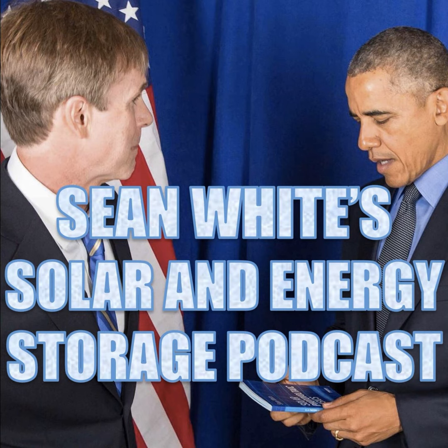Still, it's good to go back to Article 690 to learn some things, because we can see some images there which they don't have in Article 706, Energy Storage Systems. There's also Article 480, called Storage Batteries. I know it's kind of confusing - there are two different competing articles, one for batteries, one for energy storage systems. But this class is about energy storage, and Article 480 isn't really used too much. A lot of times energy storage systems are used with PV systems, but even if they're not, even if they're just supporting the grid, we can get good information out of Article 690 about how that works.